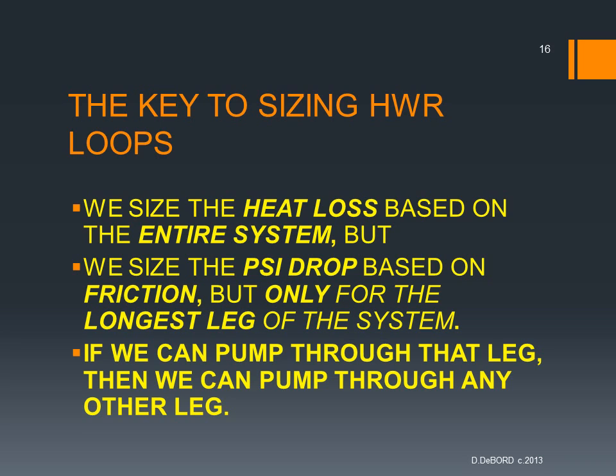Generally, the key to sizing hot water return loops is that we size the heat loss based on the entire system. All of the hot water in hot water recirculating piping is like a radiant system. It's giving off, it's losing heat. Even if it's insulated, it's losing some heat. If it's not insulated, it's losing a lot of heat. But we size for the pressure drop based on friction, of course, but only for the longest leg of the system. If we can pump through that leg, then we can get through any other leg or circuit. Remember that the water doesn't go through all of the circuits, it goes through its own circuit.